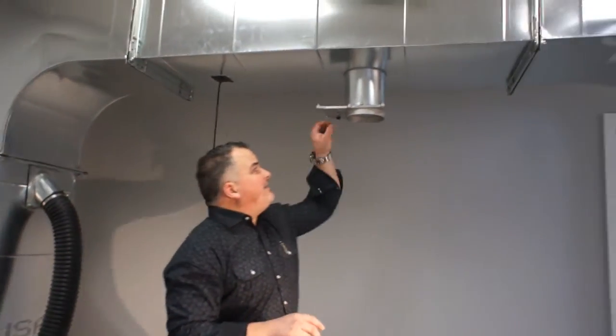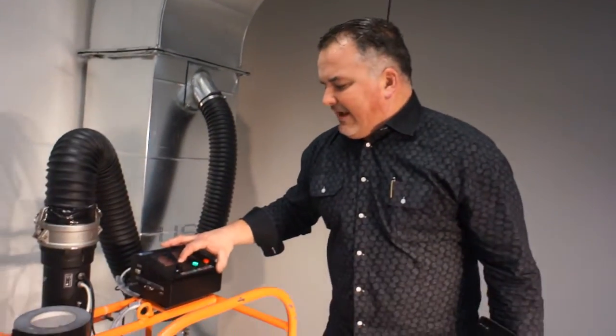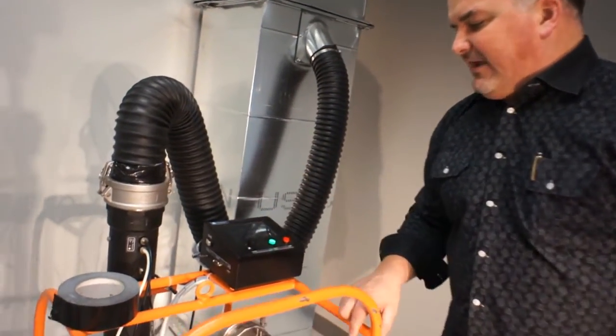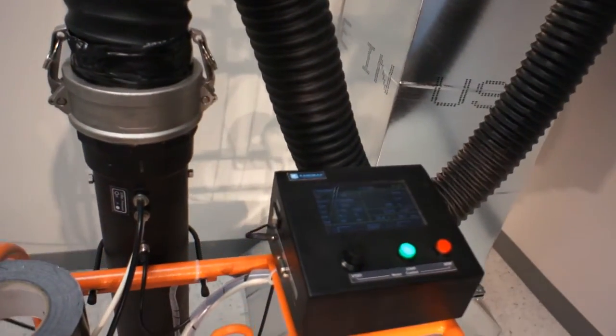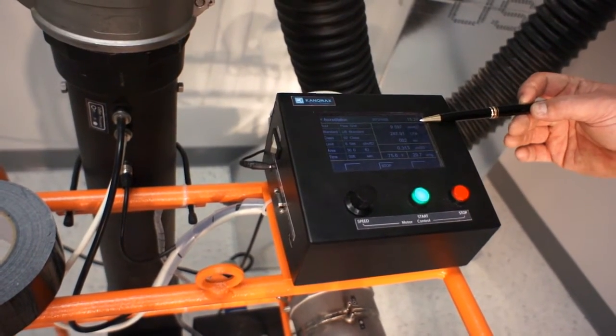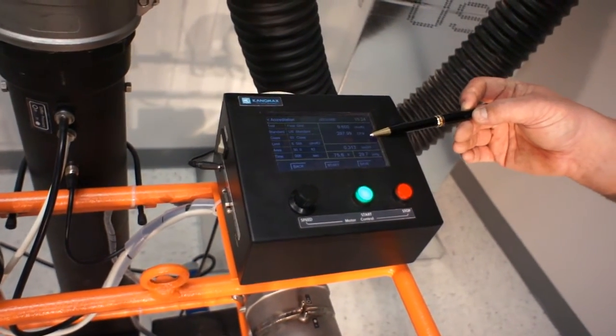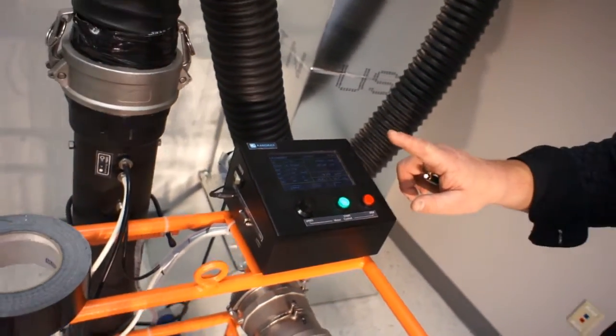We'll open up this blast gate that we have and run the same test again — six seconds. We're allowed to leak 6.58; we're leaking 9.6, so we got a fail. We're going to save it.